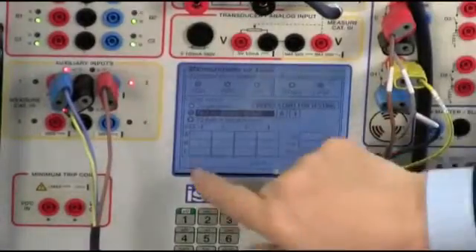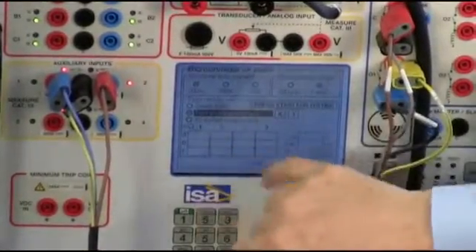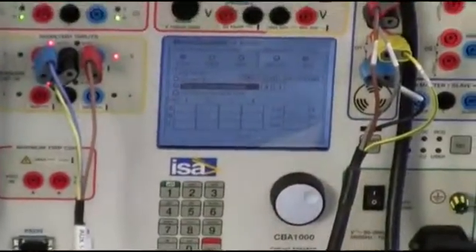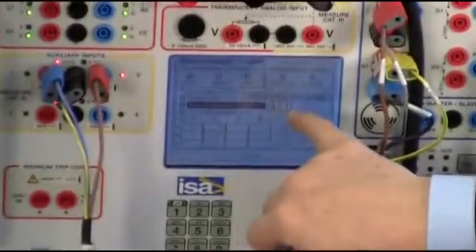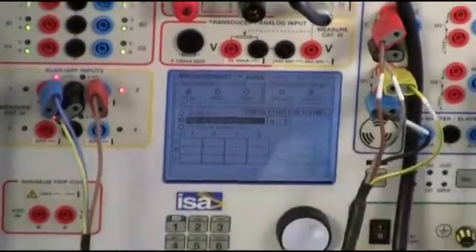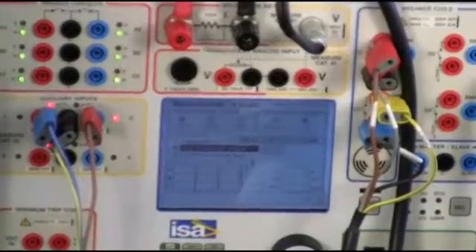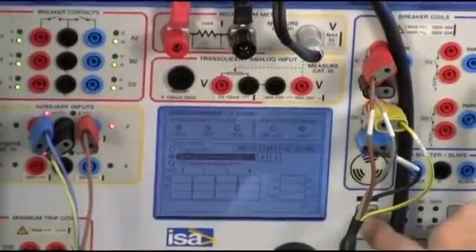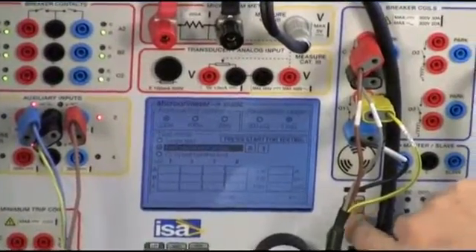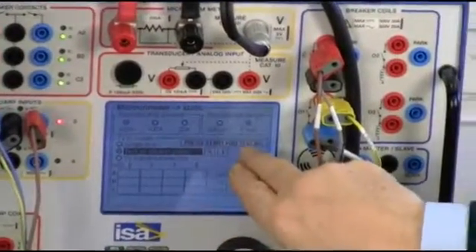As I do it, I have here a table, you see, with one, two, three, four measurements per phase. So now, for instance, I am measuring phase A, and the measurement is on contact number one, and that's it. I am already ready to press start to initiate the testing.